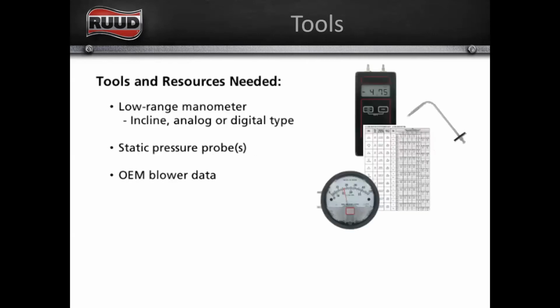So what do we need? We need a manometer, we need static pressure probes, and we need the blower data. The blower data is in the installation manual that ships with the unit. You can also access all of that information at myruud.com in the PTS section. So you go to air handlers or gas furnaces, and you look at that particular air handler, and go to the IAO, the installation and operation manual, and it's in there for all of it. If you don't have a MyRuud account, you need to get with your Tropic Supply Sales Consultant, or talk to the guys at the counter, or ladies at the counter, and they can get you set up.